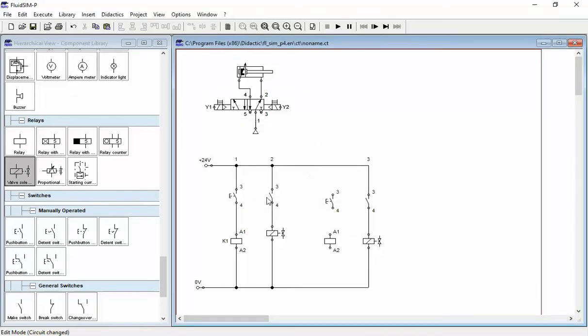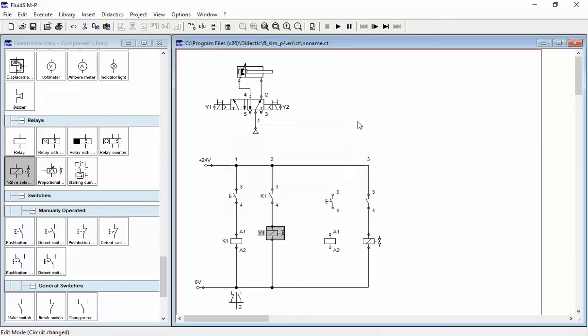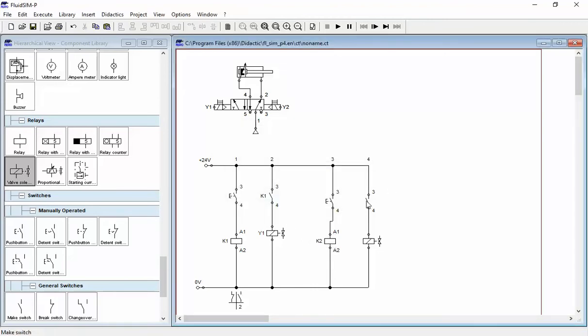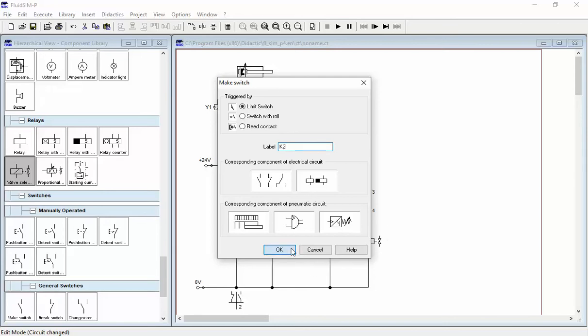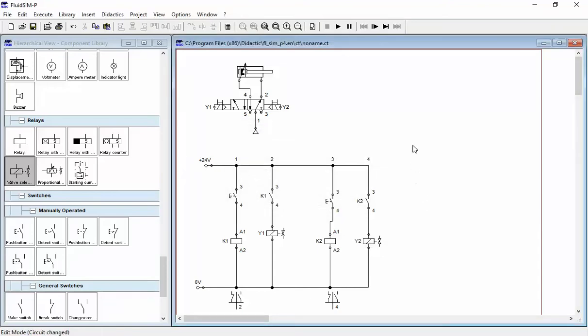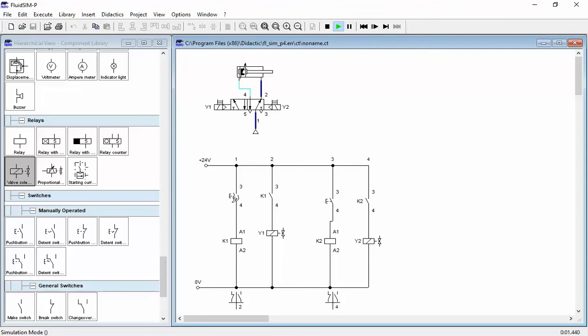And from make contact K1 to solenoid Y1 to negative by this way. Here we have relay K1 and make contact K1, and solenoid Y1 in this circuit. From here we have a second push button to relay K2, and make contact K2 to operate solenoid Y2. First one to make forward stroke, second one to make cylinder retract.